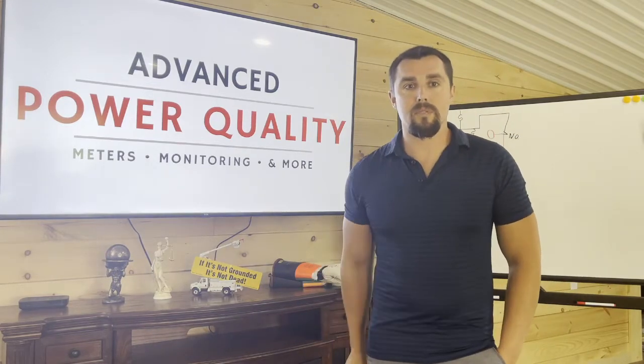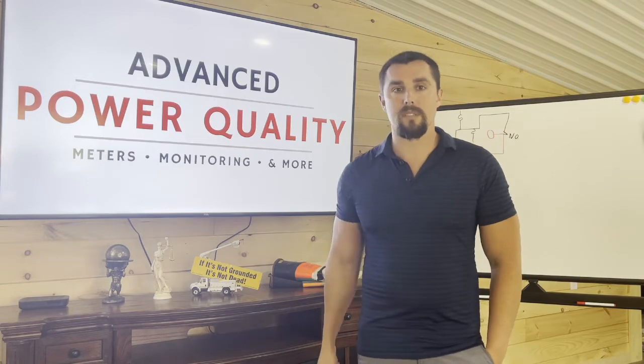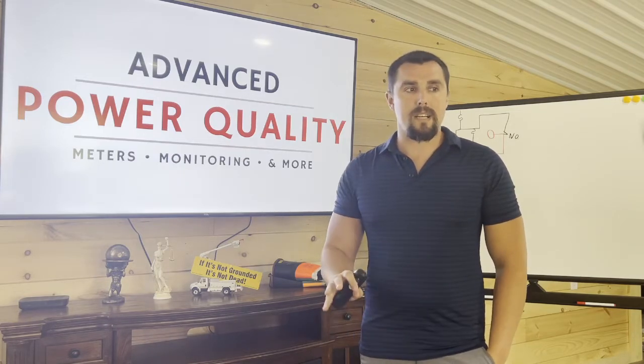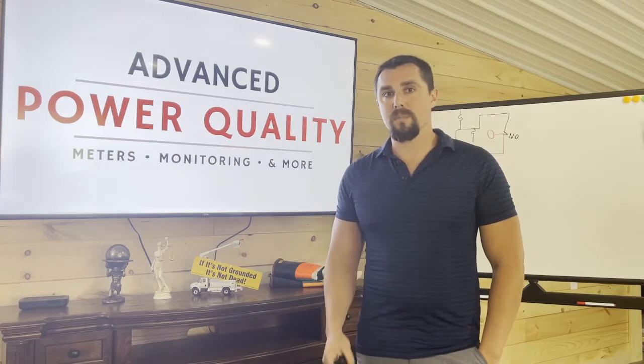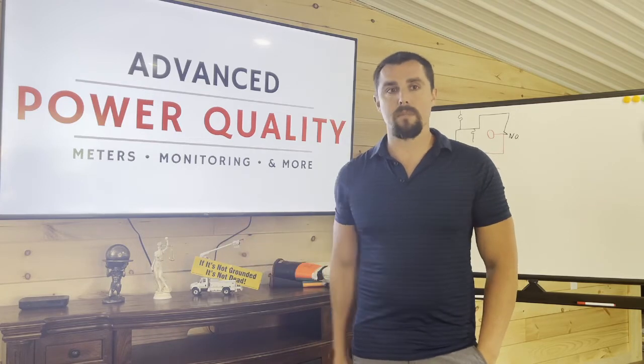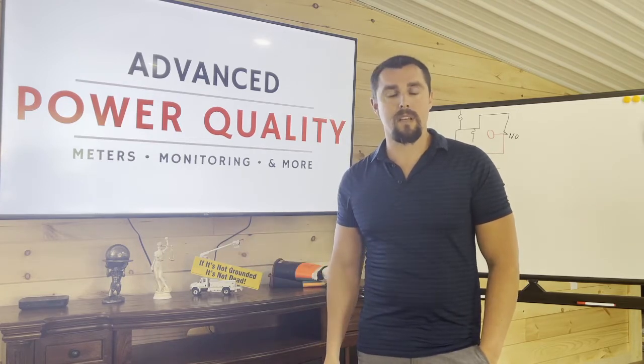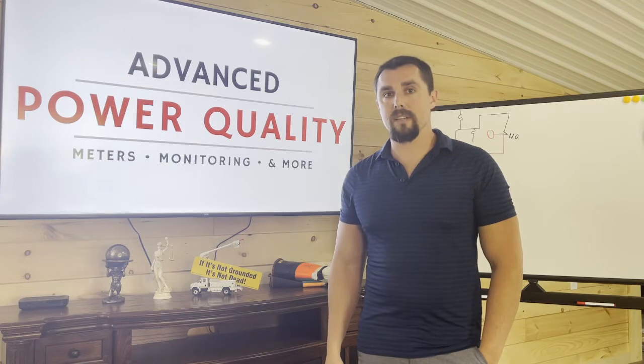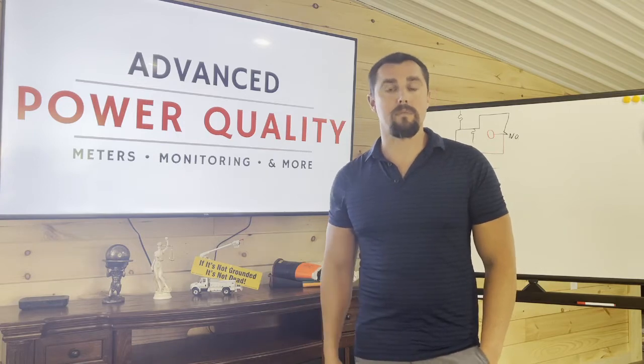Now they do sell things called static switches. They can get down to a 1 to 2 cycle transfer period, and most all your equipment is going to ride through these types of events, but they are very, very expensive, typically upwards of $1 million.